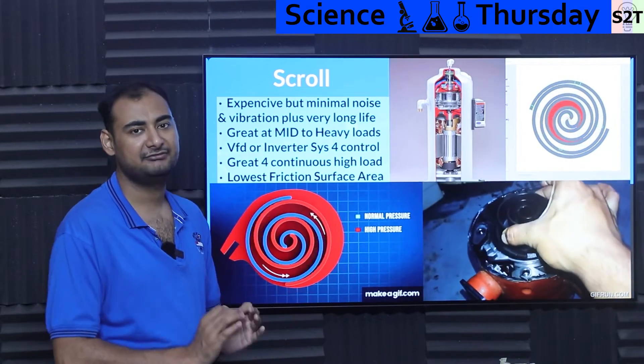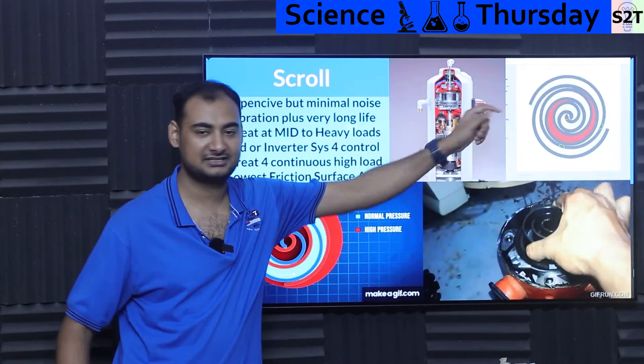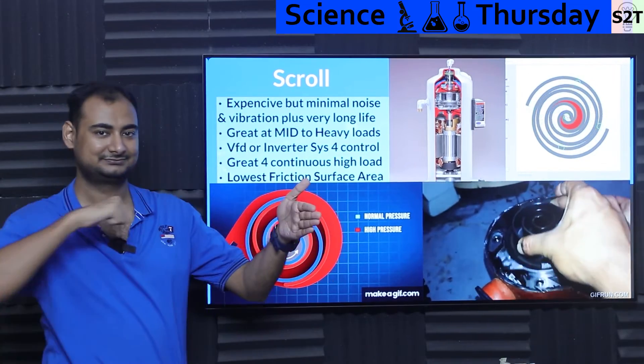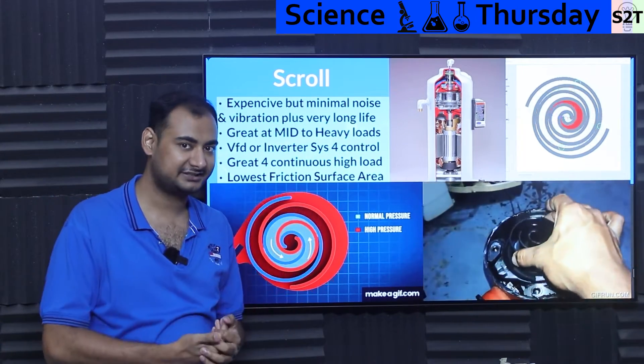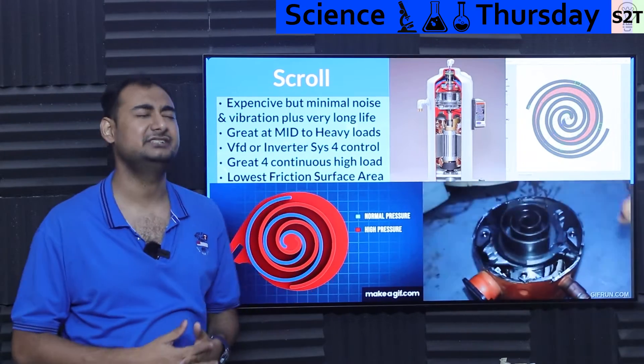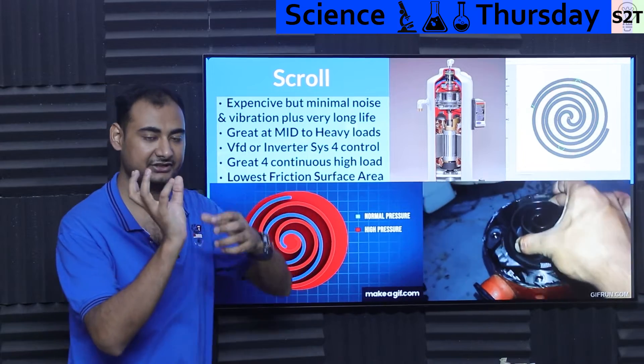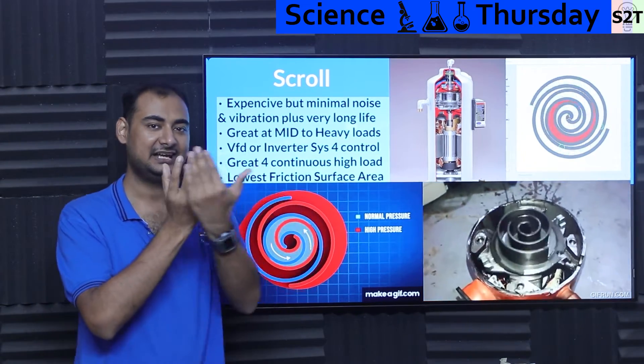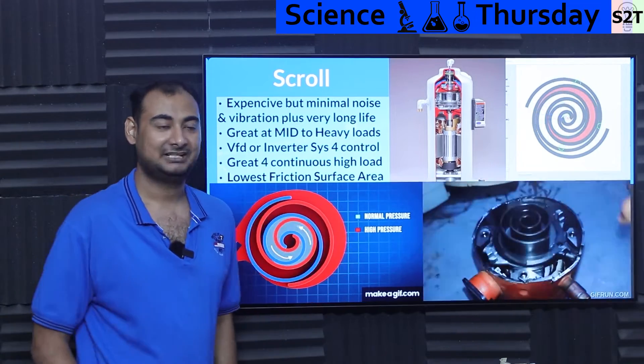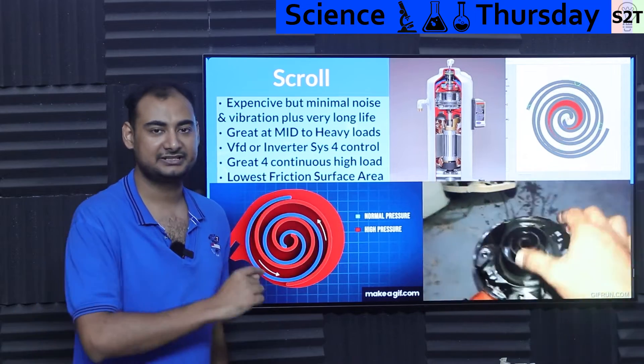The best benefit of scroll is there are virtually no friction points. It may look like it's grinding, but mathematically every contact point is circulating — essentially a roller bearing contact. The oil film that creates is more than sufficient for very long life. The shaft is eccentric, and someone figured out: put a leaf spring there. So if some liquid refrigerant gets in, no problem — it presses the spring and passes through without destroying the compressor. It's surprisingly robust in that regard, which is why you generally don't see a liquid separator on scroll compressors.